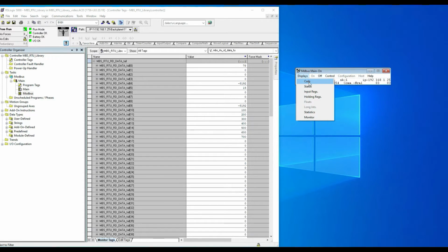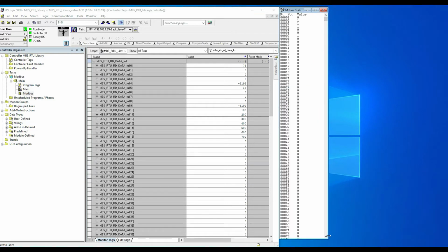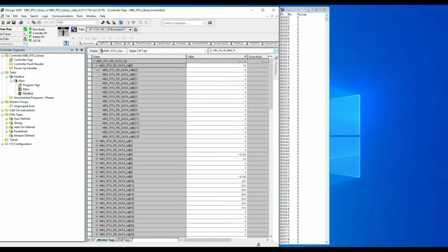So I'm going to close this for now, and first I'm going to bring our coils that we were trying to read. Minimize that for a second, put that a little bit down like that. As we mentioned, these coils, because we're reading 80 coils, are going to occupy essentially these first 4 registers. If we see here we have 0, 1, 1, 1, 0. If we open up the first register, you can see it's matching 0, 1, 1, and then 0, 0, 1, which is matching what we have in here.